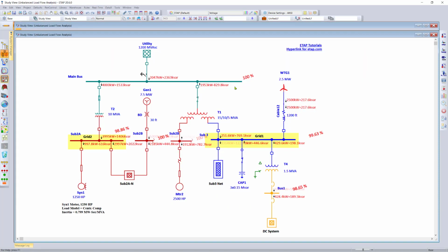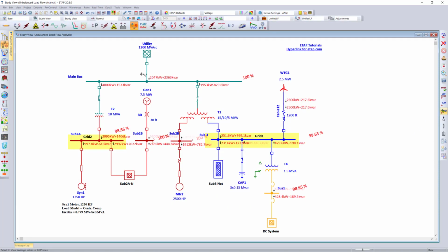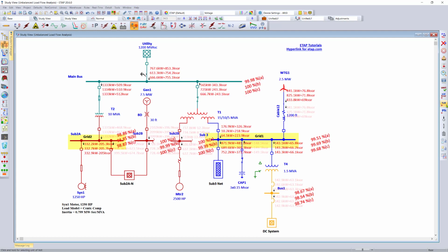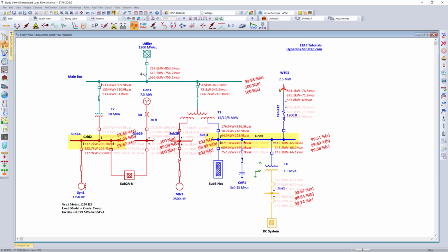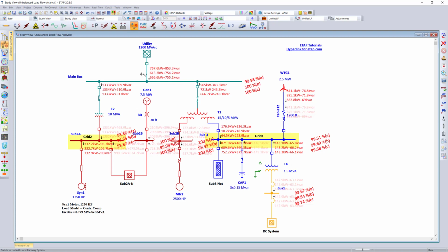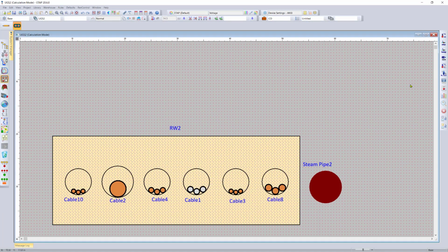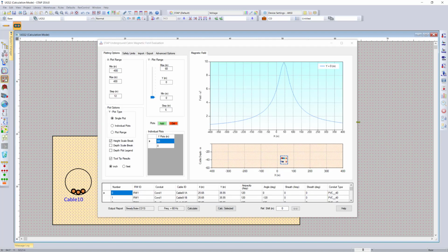So you can simply go to the one-line diagram, run unbalanced load flow calculation, where you can see your average values or the phase values along with the current angles, which can be visualized directly onto the one-line diagram. You can then take this information, update it into the underground raceway program, and make it available for both the thermal calculation as well as the magnetic field calculation. The thermal calculation quickly gives you the current versus temperature, while the magnetic field calculation provides you with the magnetic field intensity strength for that particular raceway.